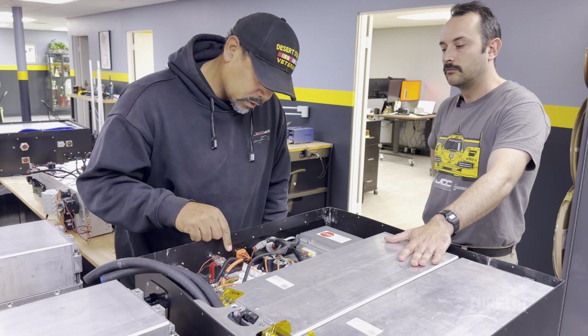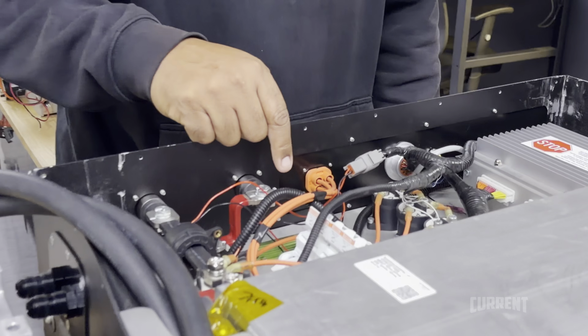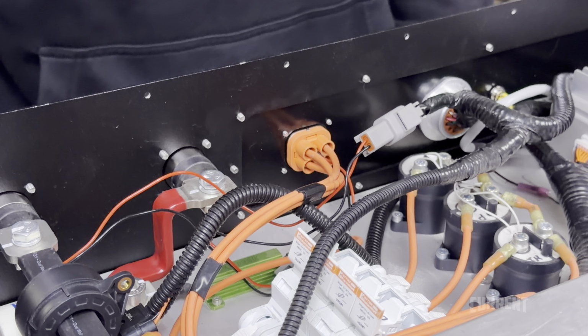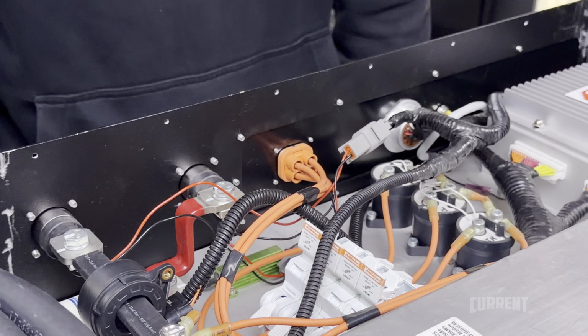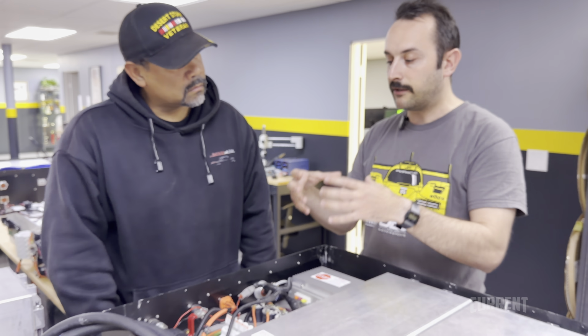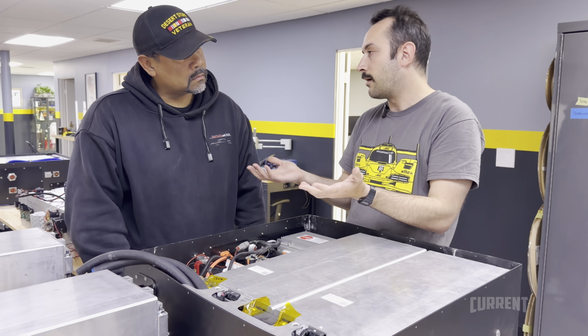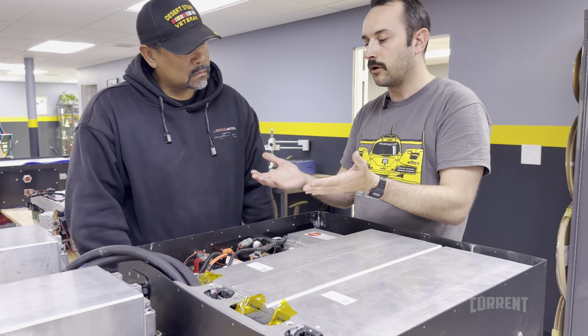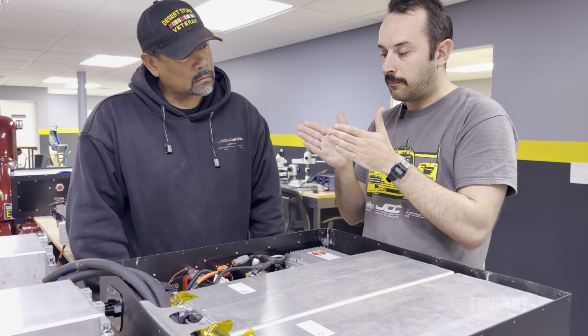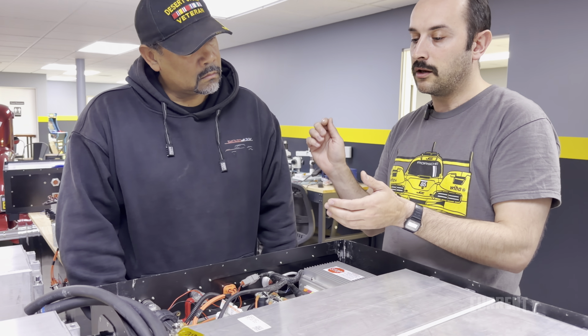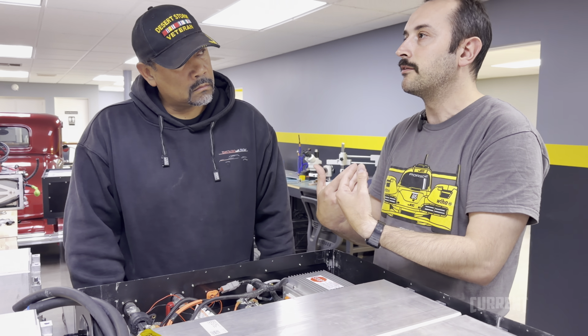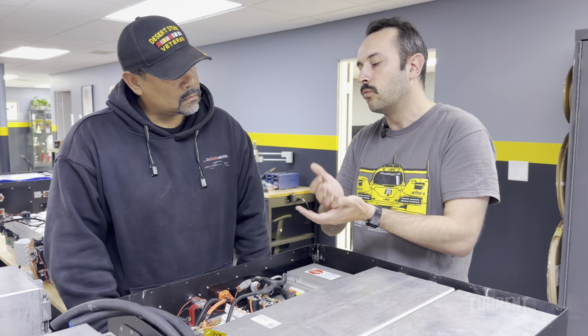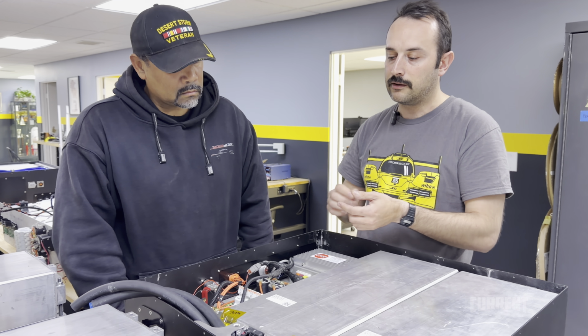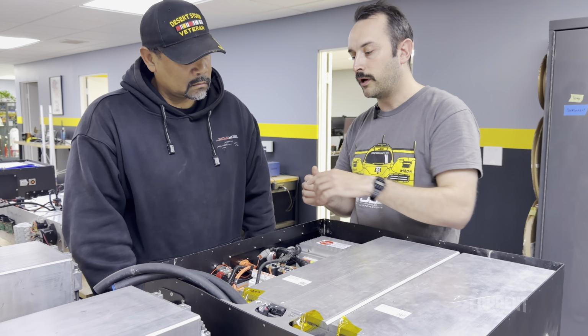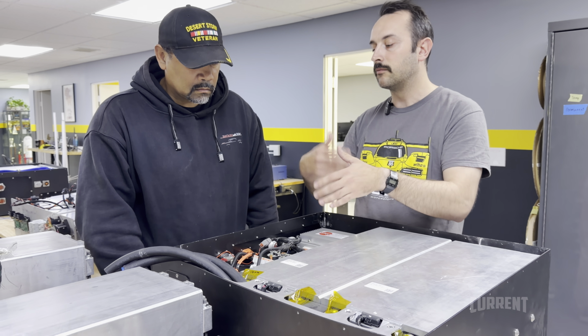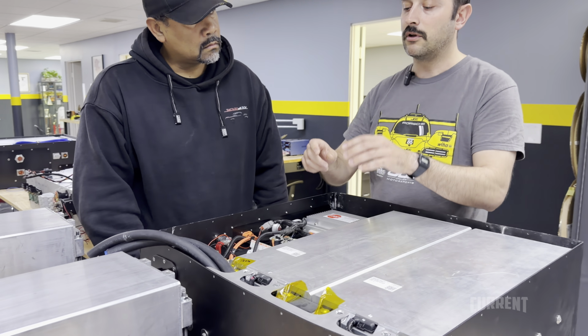Let's go back to this pre-charge resistor. Why would I need one if all the current's going through there anyway? Because the moment you close the contactor, the capacitor of the inverter is normally empty since there was no current before. A capacitor that's completely empty, when you suddenly give it current, is basically a short circuit. That means you'll get a spike in current that could damage your circuit - maybe not the first time, but doing it more and more will damage it.